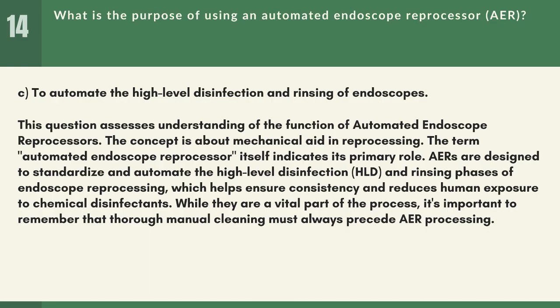This question assesses understanding of the function of automated endoscope reprocessors. The concept is about mechanical aid in reprocessing. The term automated endoscope reprocessor itself indicates its primary role. AERs are designed to standardize and automate the high-level disinfection, HLD, and rinsing phases of endoscope reprocessing, which helps ensure consistency and reduces human exposure to chemical disinfectants. While they are a vital part of the process, it's important to remember that thorough manual cleaning must always precede AER processing.